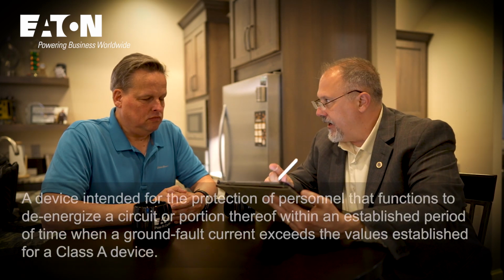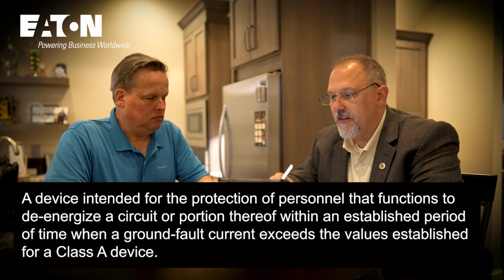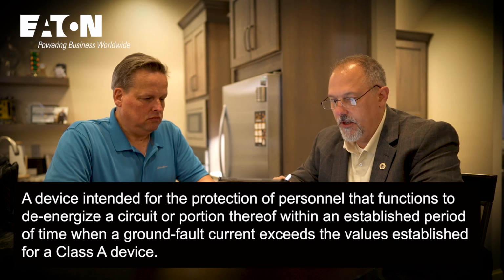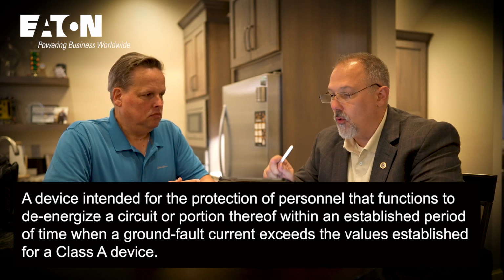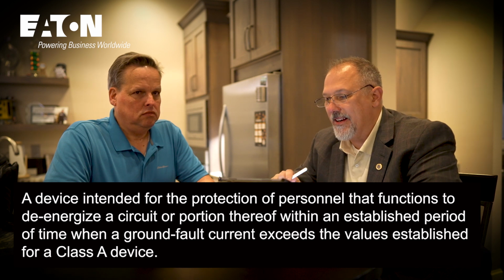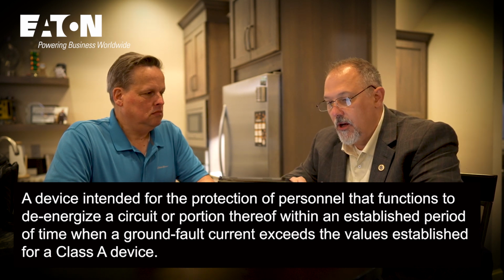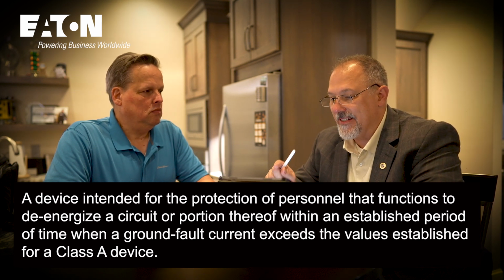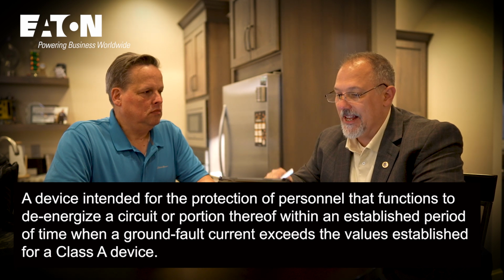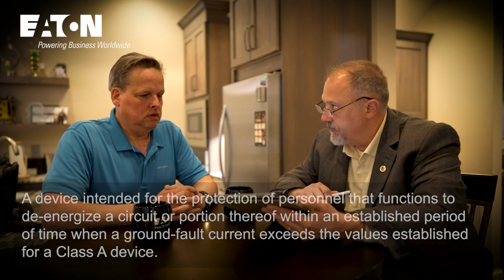I'm going to read the definition of a GFCI, ground fault circuit interrupter. A device intended for the protection of personnel that functions to de-energize a circuit or portion thereof within an established period of time when a ground fault current exceeds the values established for a Class A device. Right. So anywhere this term is used in the code is a ground fault circuit interrupter. We're talking about Class A devices, and that was clarified recently. Yes.